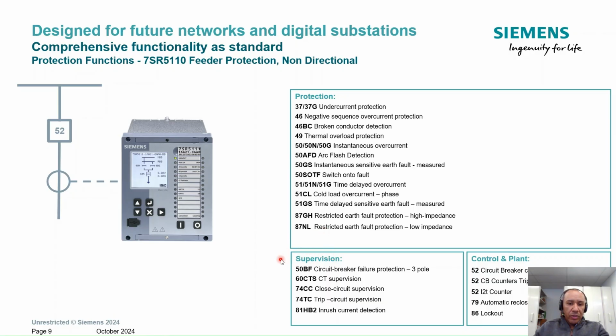Okay, supervision for trip coil, close coil, and circuit breaker fail, CT supervision, and inrush detection are possible on this device, and also the control of the circuit breaker. Okay, you have the control of the circuit breaker, you have the open, close, and lockout on this device.